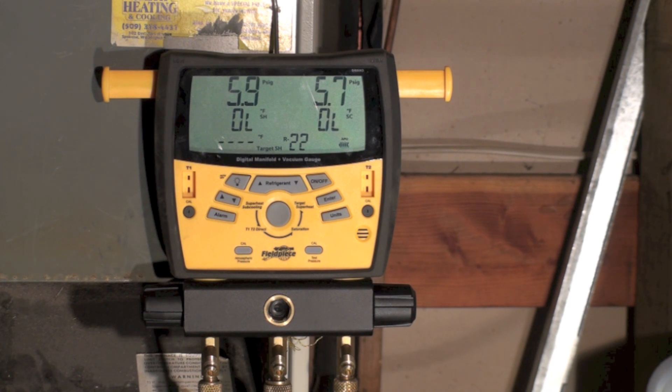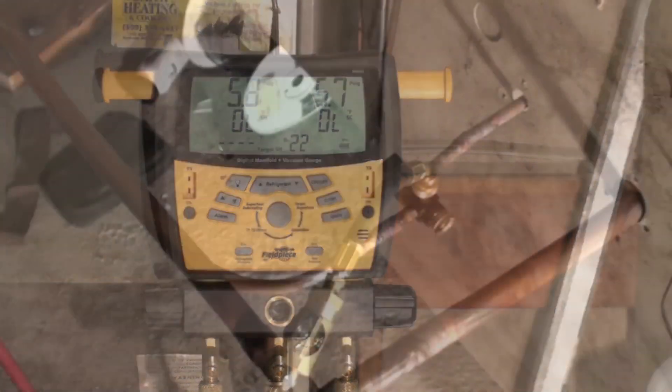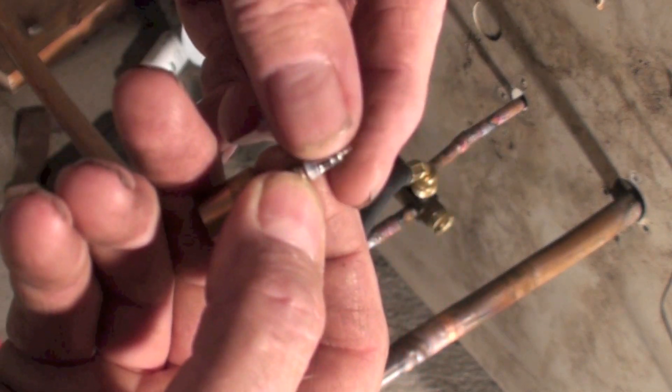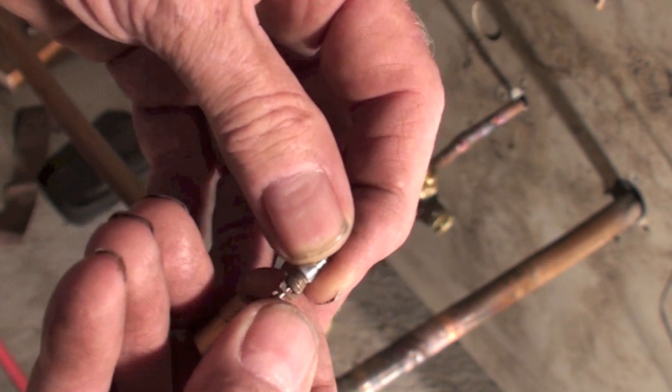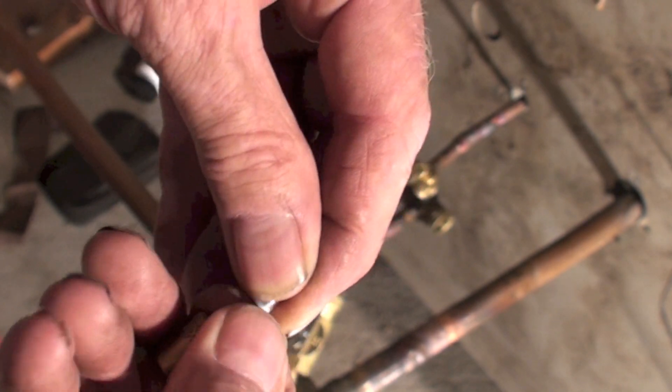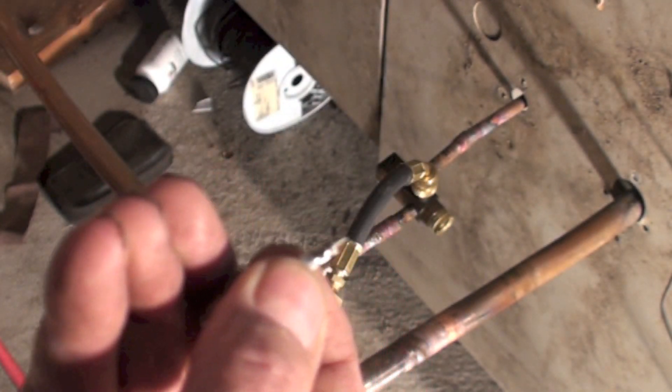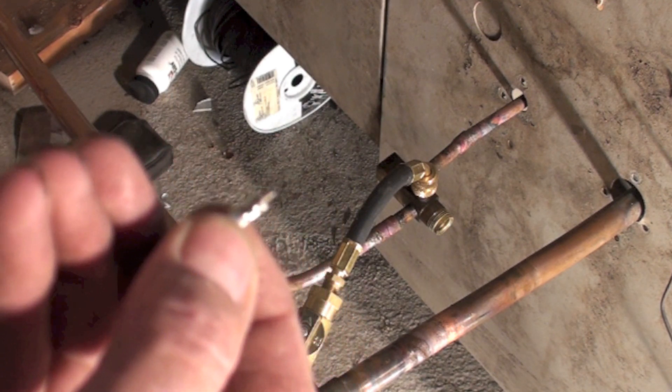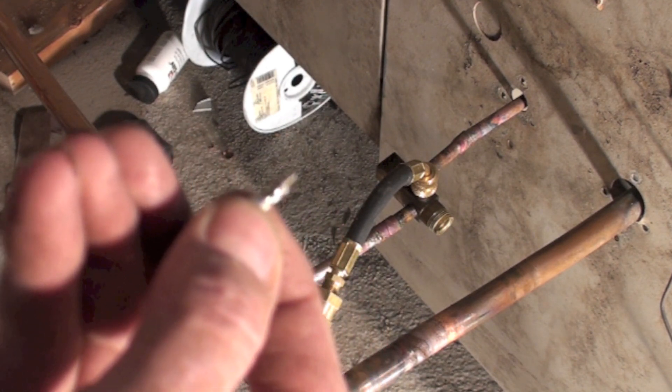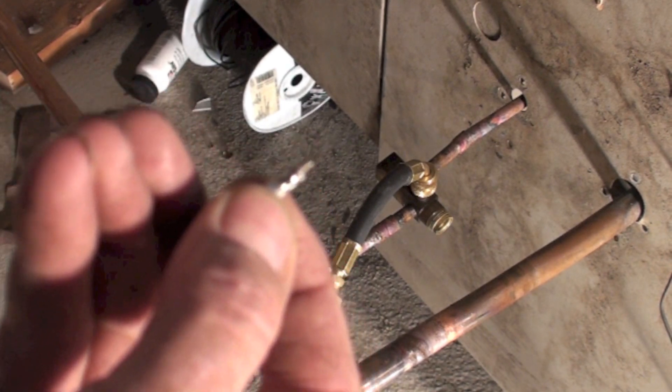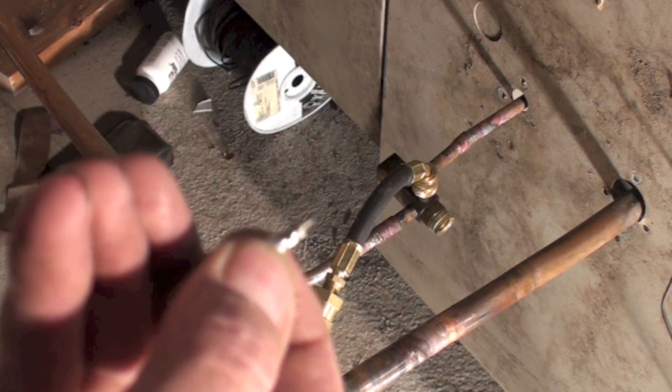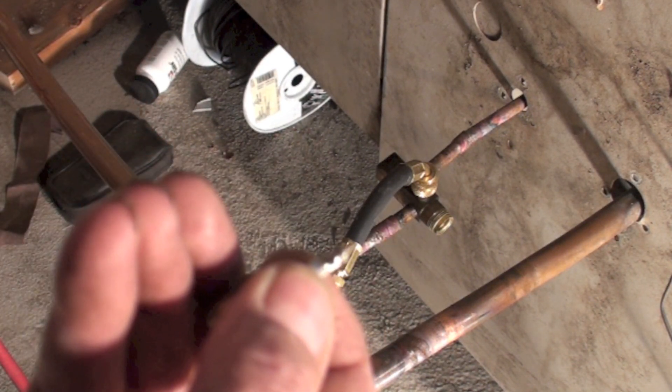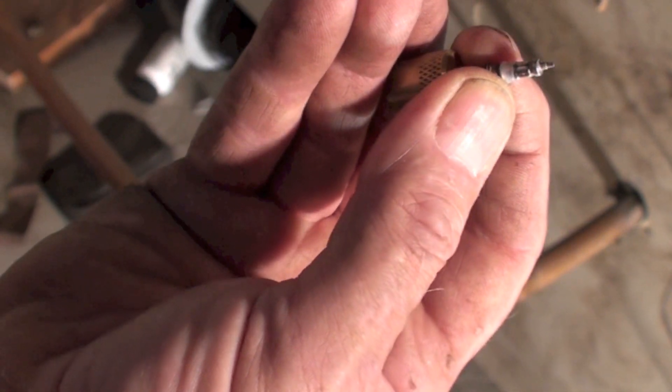Okay, now I've got my Schrader ready to put in. I use brand new Schraders each time. I throw the old ones away just simply because they're not clean. They've been rolling around the dirt or whatever. I throw them away, putting new ones in because it's a real cheap part and there's no reason not to. You can charge the customer for putting them in, but you can't charge him when you come back and got a leak. So anyway, there's the Schrader.